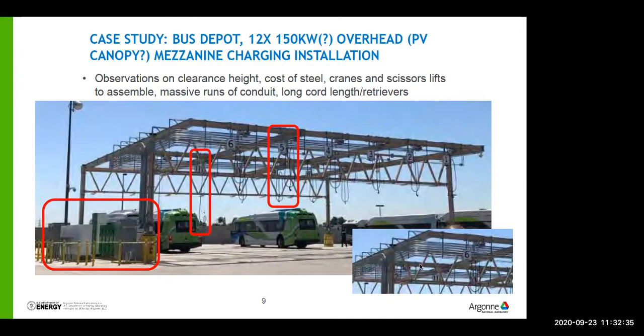It shows the cable extended and plugged into the bus. Just to the right of that box, you can see them pulled up to the gantry, and this has 12 charge ports, and then probably literally a mile of conduit to go from the boxes on the left, which are the switchgear and power electronics. Most of your utilities, when I say switchgear or panel board, I assume you know what I'm talking about - these gray boxes that bring in the power and turn it on and off safely - to the power electronics, which are green boxes that convert it from medium voltage to between 400 and 1,000 volts DC. Next.